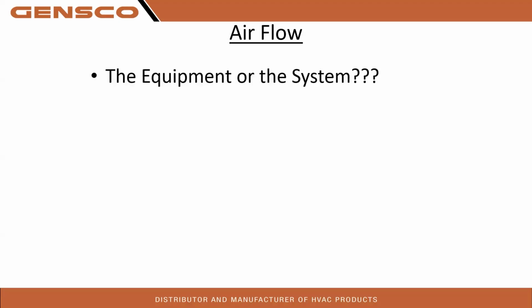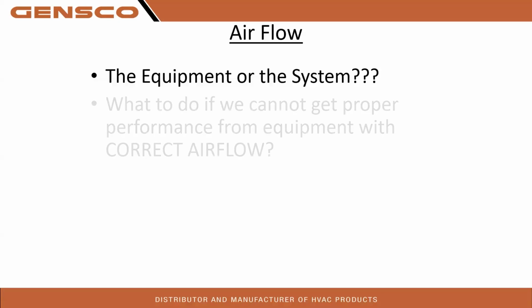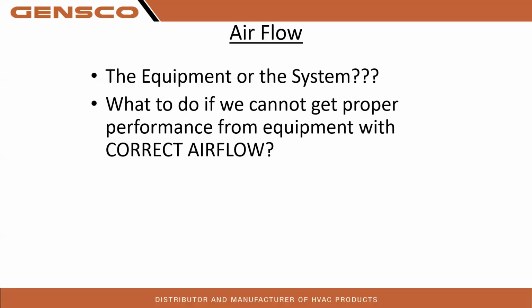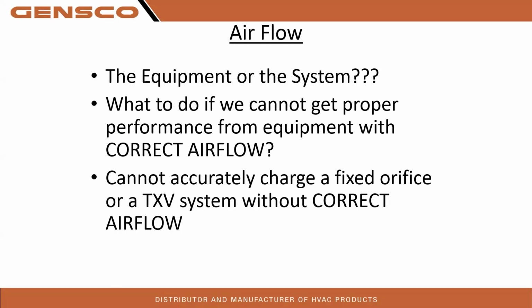So is it the equipment or the system, right? Airflow. Airflow will take out a compressor. It'll lead to discomfort in the house, premature failure. So is it the equipment or the system? Everybody likes to kick the equipment pretty quick. We always need to dive a little bit deeper and see what's going on with the ductwork. So what do you do if we cannot get proper performance from the equipment with correct airflow? You're not going to be accurate. Without correct airflow, you will not be able to accurately charge a fixed orifice or a TXV system.